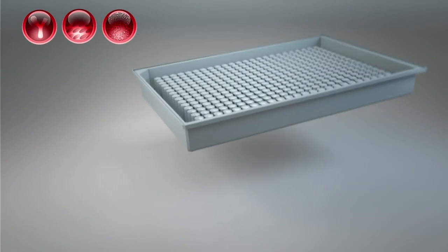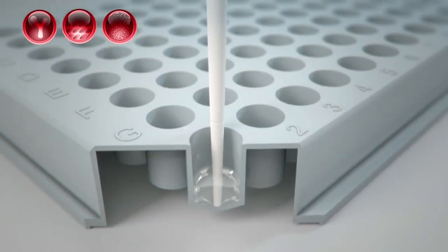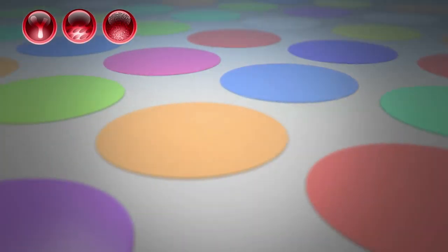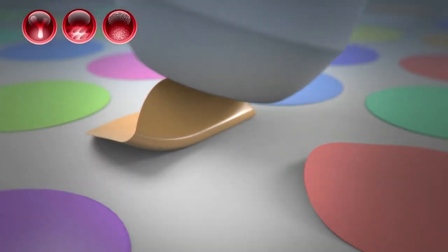As a result, conventional washers require more washing steps for higher-density plates, and it becomes more difficult to avoid touching the bottom with the aspiration needle.